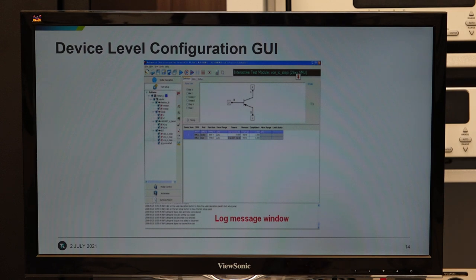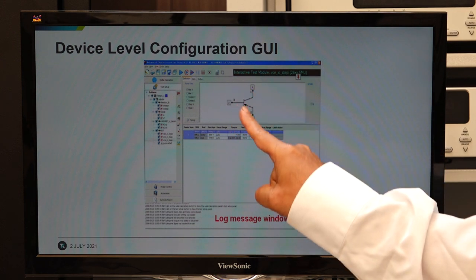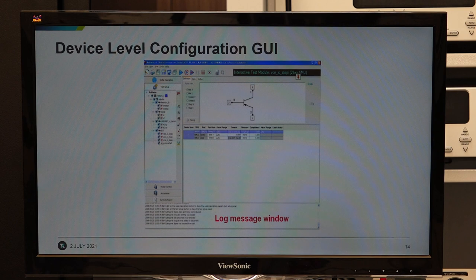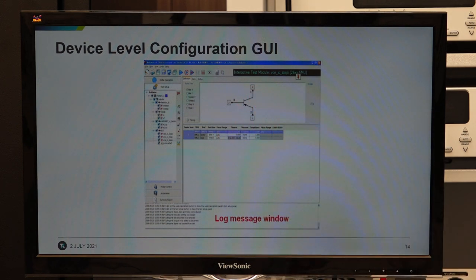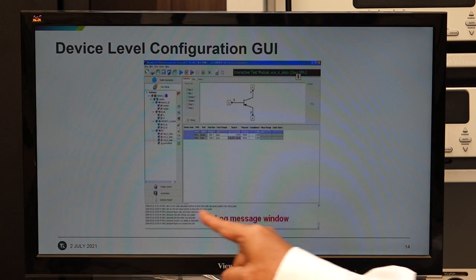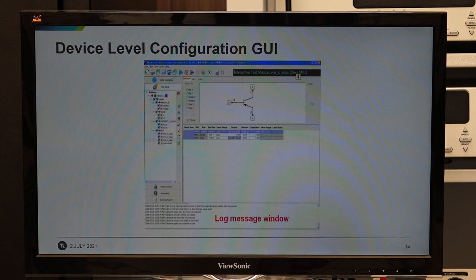This example screen shows device level setup. There is a bitmap of the device structure, all tests being done are listed, and there is a facility to assign the SMUs for each device contact pin. When the test is running, the current log messages show whether the test has passed, failed, or has been stopped because of excess current flowing into the device or because current limits have been exceeded.